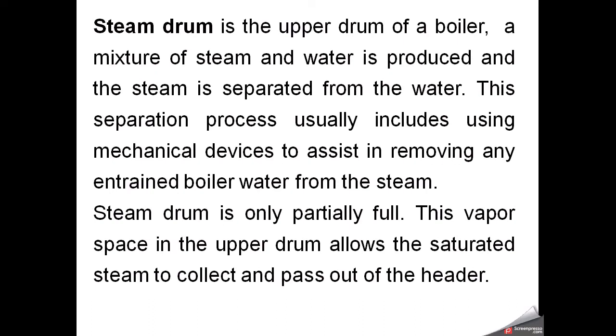The steam drum is the upper drum of the boiler and is the first part where steam appears. A mixture of steam and water is produced here, and the steam is separated from the water using mechanical devices that remove any entrained boiler water from the steam. The steam drum is not completely filled but is partially full, with space available for steam. This vapor space allows saturated steam to collect and pass out of the header.